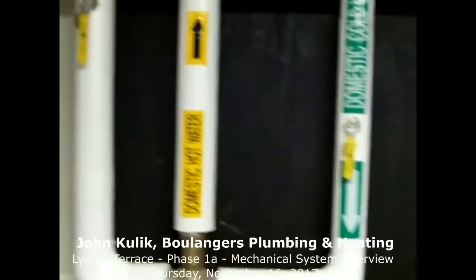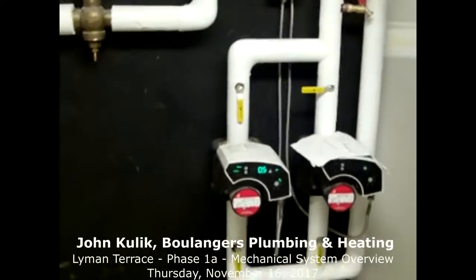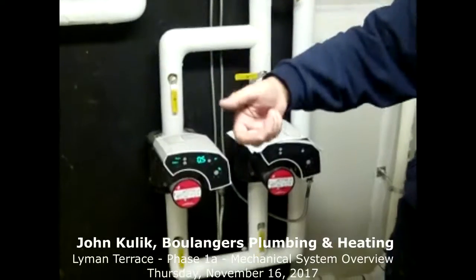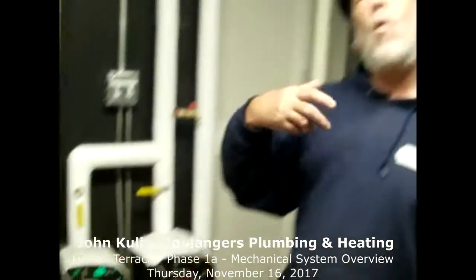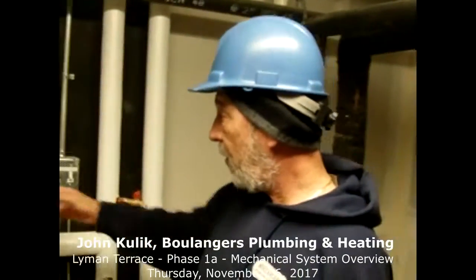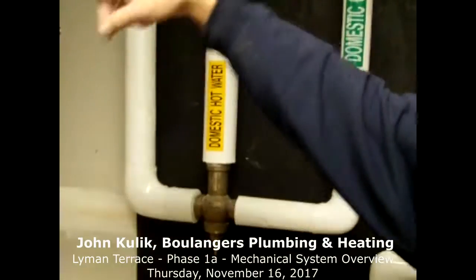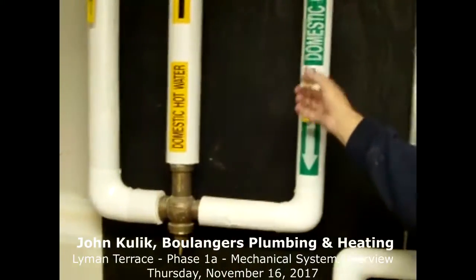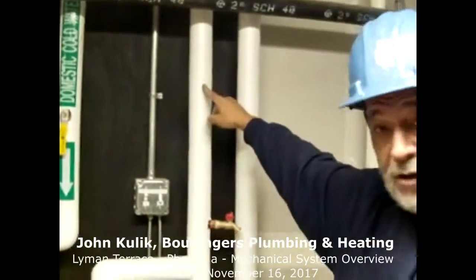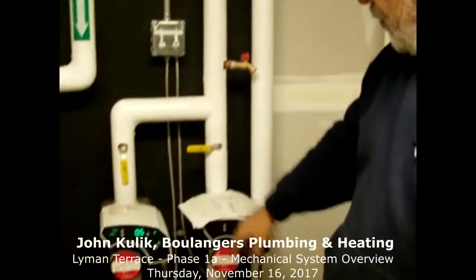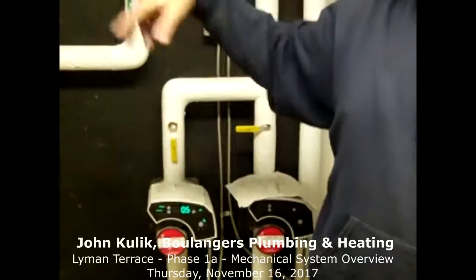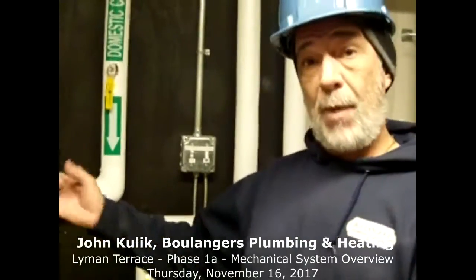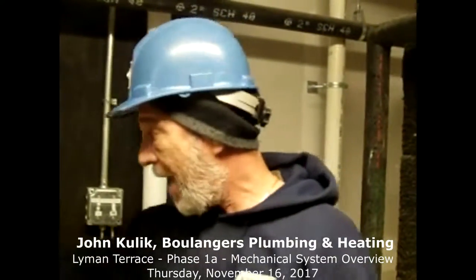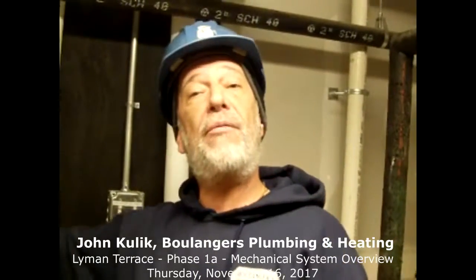Got it. These pumps here are what bring the water around the building so that it's almost instantaneous use of hot water out the faucet so it won't run down the drain. What happens is at the very end of the last fixtures on each end of the building, there's piping T's put in that are brought back to this recirculation line. This pulls the water around the building back through and remixes it so you stay with a mixed loop temperature even on the non-draw time. When the people draw by opening their faucets, it gets a pressure drop. That's what activates the springs inside here to allow the water to flow through the mixing valve. And there we have it.